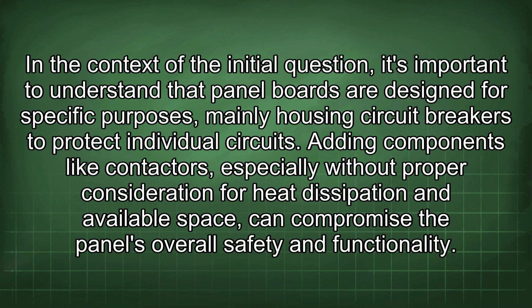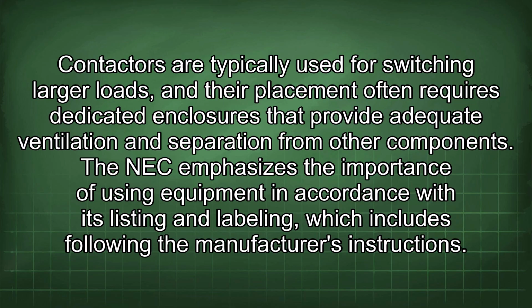In the context of the initial question, it's important to understand that panel boards are designed for specific purposes, mainly housing circuit breakers to protect individual circuits. Adding components like contactors, especially without proper consideration for heat dissipation and available space, can compromise the panel's overall safety and functionality. Contactors are typically used for switching larger loads, and their placement often requires dedicated enclosures that provide adequate ventilation and separation from other components.